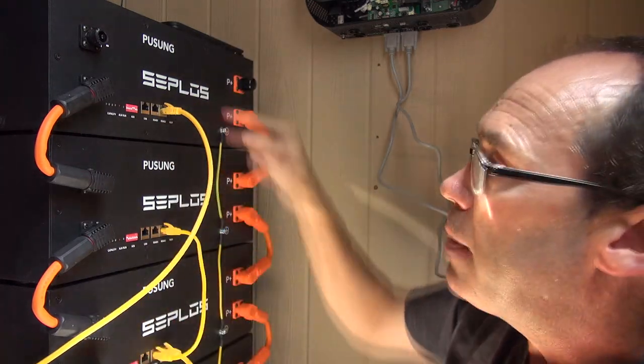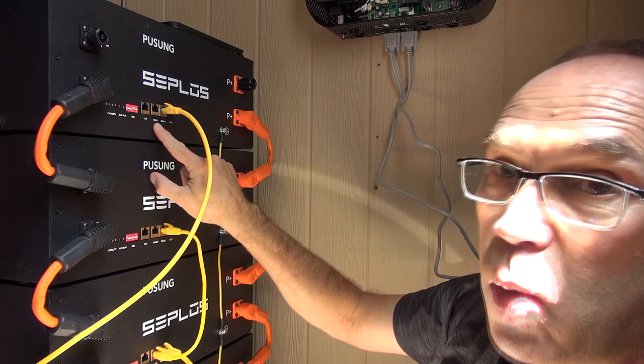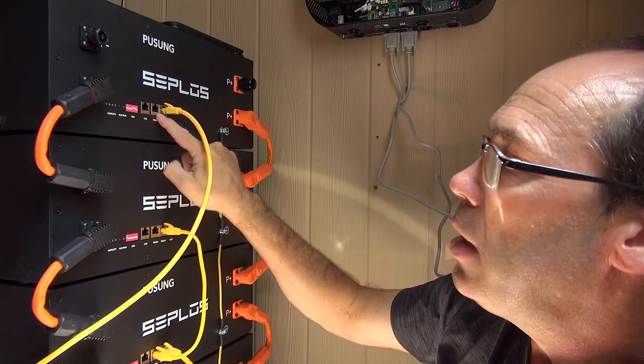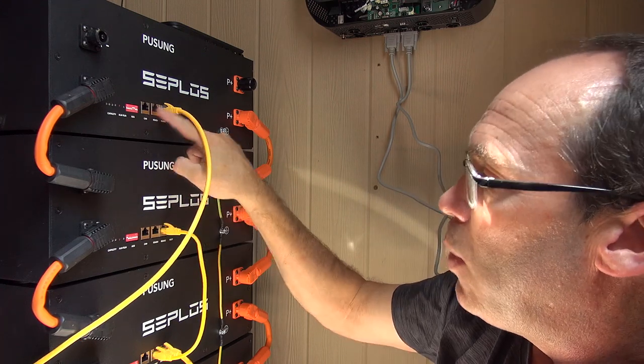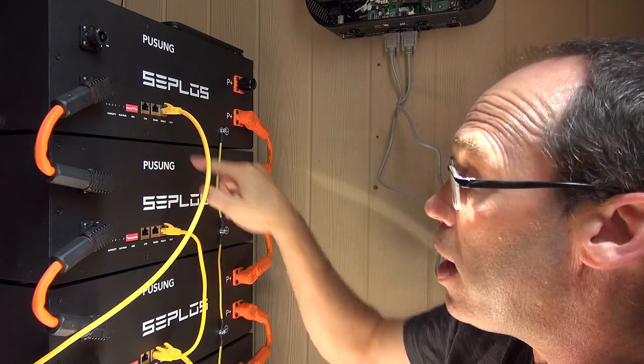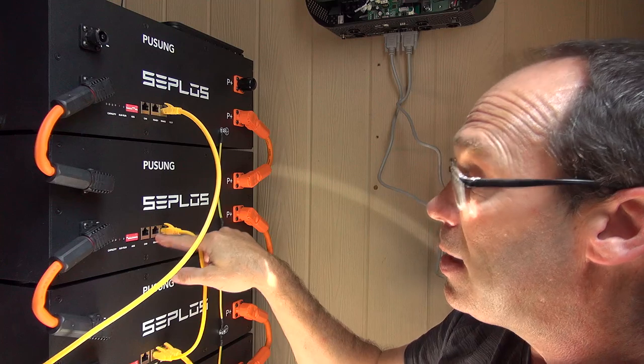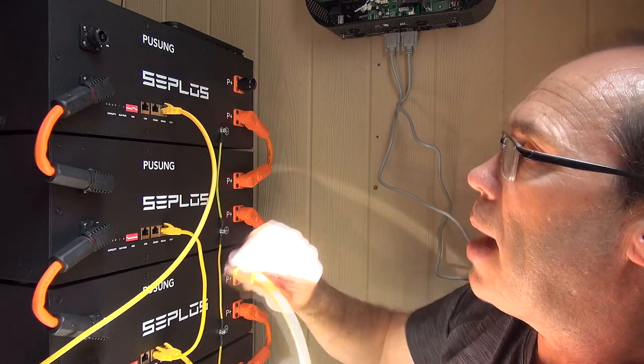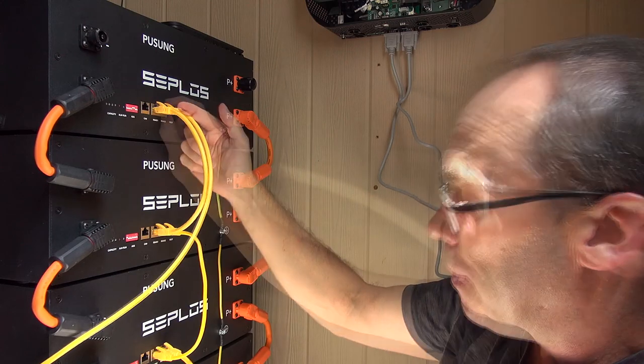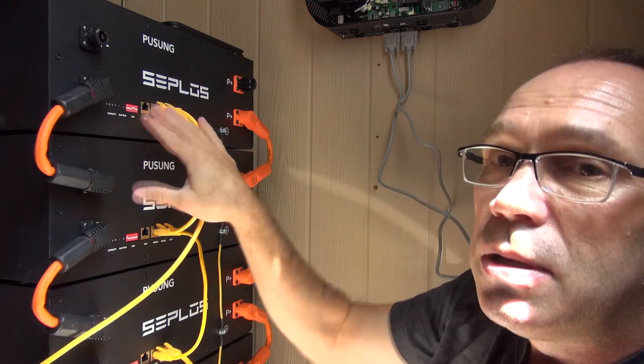Once you've got all your interconnects connecting the packs in parallel, you then use the shorter RJ45 cables to connect between the batteries for RS485 communication. On the battery you'll see RS485 port 1 and RS485 port 2 — to the best of my knowledge these are common, so it doesn't matter whether you loop straight down or go crossways. In their video Seplos tends to go in a cross pattern. I've tried it different ways and it still communicates, so I believe all the RS485 ports are common.